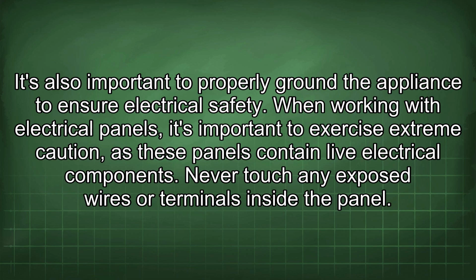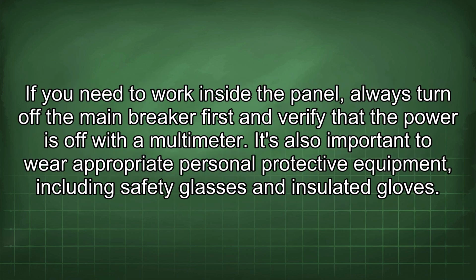When working with electrical panels, it's important to exercise extreme caution as these panels contain live electrical components. Never touch any exposed wires or terminals inside the panel. If you need to work inside the panel, always turn off the main breaker first and verify that the power is off with the multimeter. It's also important to wear appropriate personal protective equipment, including safety glasses and insulated gloves.